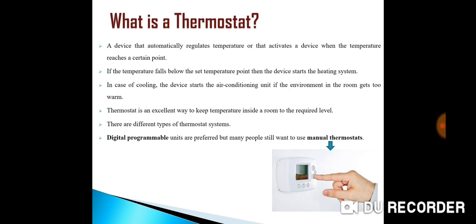A thermostat is an example of a bang-bang controller, as the heating or cooling equipment output is not proportional to the difference between the actual temperature and the temperature set point. Instead, the heating or cooling equipment runs at full capacity until the set temperature is reached, then shuts off. The rate at which the target system temperature can change is determined both by the capacity of the heating or cooling equipment to add or remove heat, and the capacity of the target system to store heat.